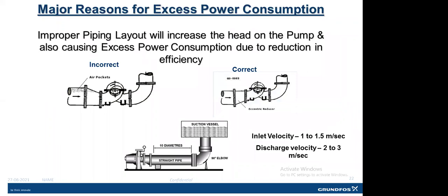So this is a general thumb rule. At the pump inlet, the water velocity should be 1 to 1.5 meters per second, and for the pump discharge, the velocity should be 2 to 3 meters per second. And also for pump suction, always use an eccentric reducer as per the guidelines given by the pump supplier. Whether this reducer is to be kept at the top or bottom depends on the suction condition, so always check the guidelines. If it is with negative suction, the right placement would be like this. The bend should be from below.